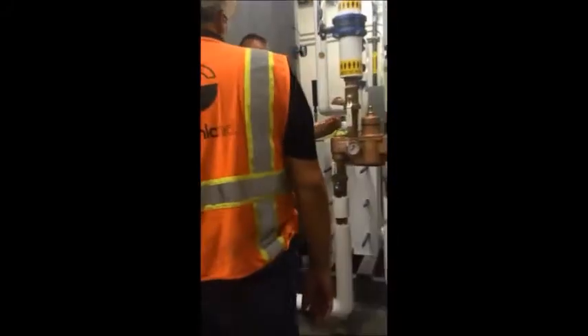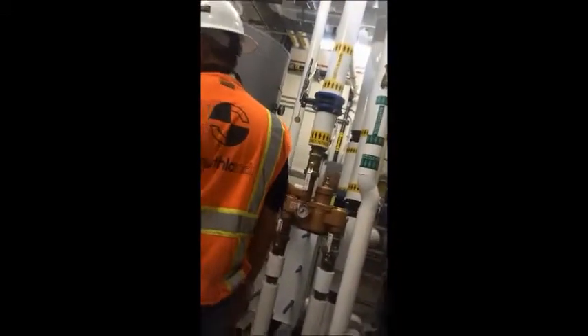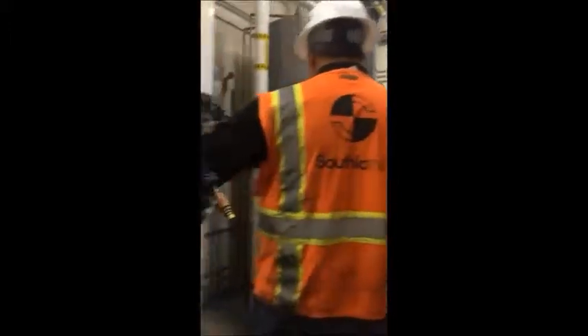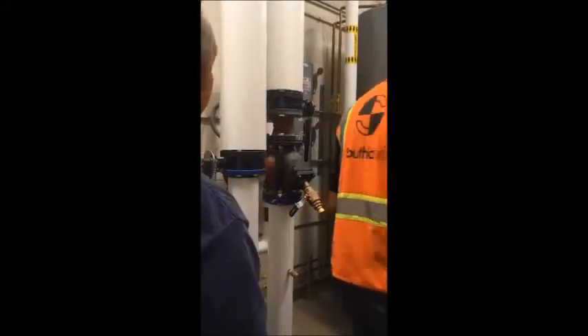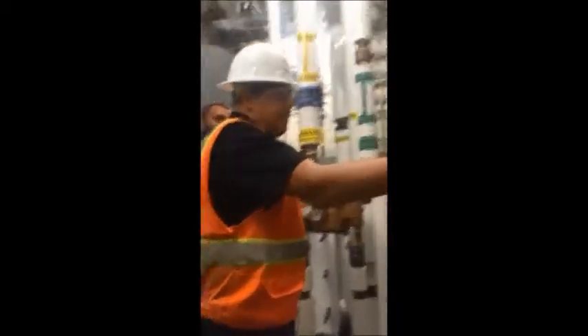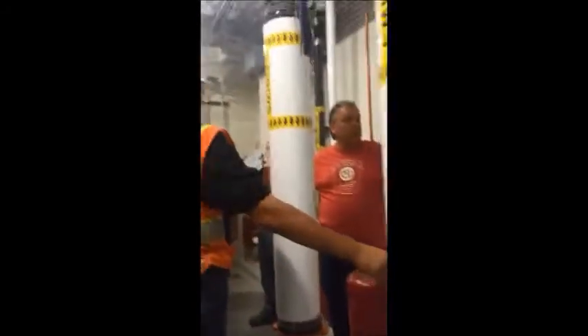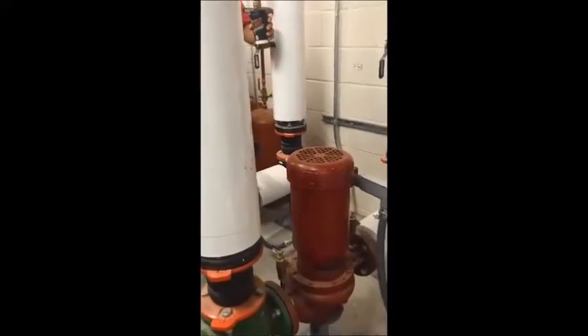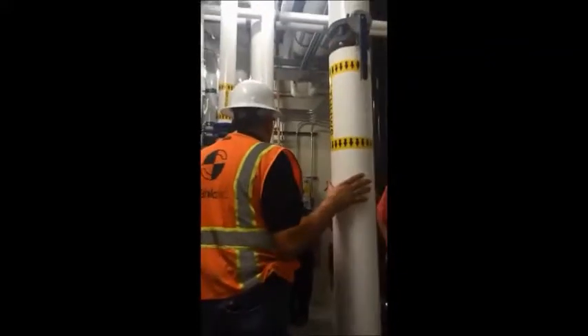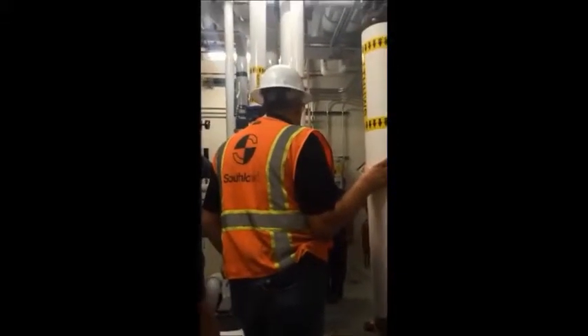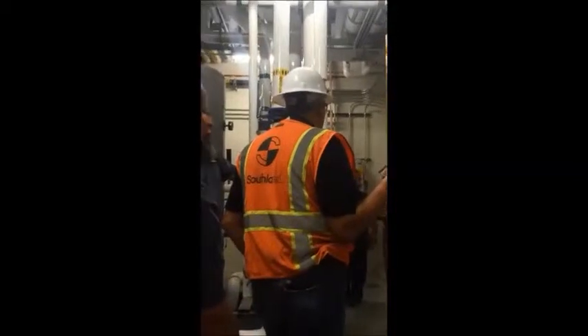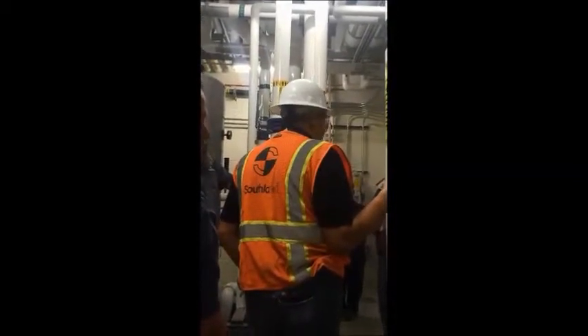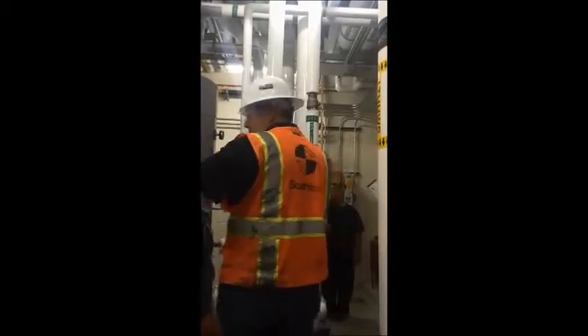Air separator for the chill water. Air separator for the low temp heating hot water. Again, this is your heat exchanger for your heating on your chill beams. So you have high temp hot water, and then low temp hot water, and the 2 pumps that support the chill beam units. Obviously, if there's no demand request, it's not going to start the pumps up to provide heating to the chill beam units. We're 120, 140? 100 degrees on the chill beam. Yeah, low temp hot water. Right. High temp hot water comes from your facility, which would be like 180. Correct. So 180 here and 100 here.